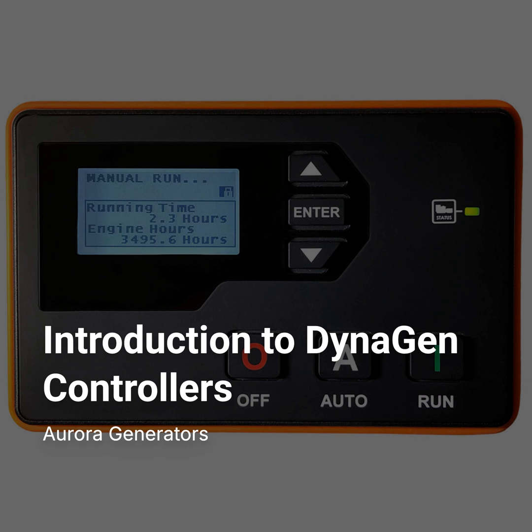Users can often manually request DM2 codes, the more detailed fault codes, with a button press. And for modern engines with DEF SCR emission systems, the exhaust fluid systems, the controllers can offer monitoring and control functions for those too. Finally, DynaGen has its own proprietary PGNs, parameter group numbers within J1939, allowing broadcasting of specific data and remote control of the controller itself over the network.